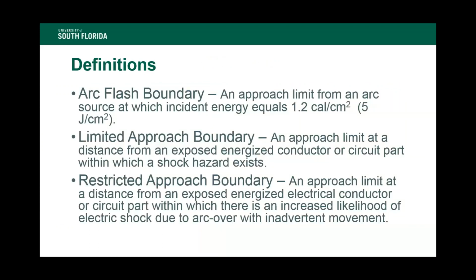Continuing with the definitions, arc flash boundary is a limit to how close you can come to an arc source, and they measure it at the threshold of where the energy from the arc measures 1.2 calories per square centimeter. If you want to know how much that really refers to, 1 calorie is a measurement of energy which is used to raise the temperature of 1 gram of water 1 degree Celsius. So it may not seem like much, but when you think about this level of energy applied over an area of maybe a couple hundred square centimeters, it adds up to a considerable amount of energy.